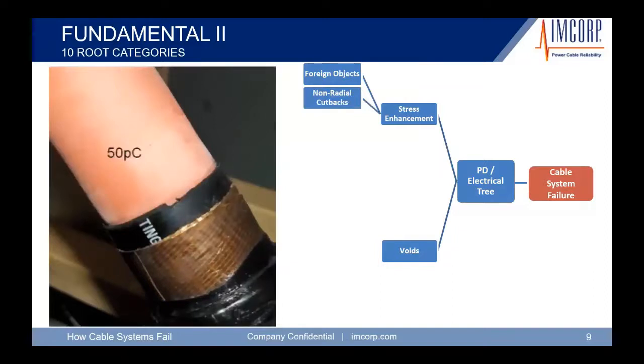Our second application, our second stress enhancement, here is where terminators usually make their money, right here. If they can make a nice ring cut, which is recommended by all manufacturers of components. So when you make that cutback, you have to have a nice, smooth ring cut. You can't have any lips right here. These lips, if you leave that unattended and you don't have any void filler in there, that's a concentration of electrical stress. Again, that electrical stress is stronger than the dielectric strength of the insulation. So eventually, even an EPR will begin to create a carbon tree that will create a path from the inner conductor to the outer conductor, causing failure.